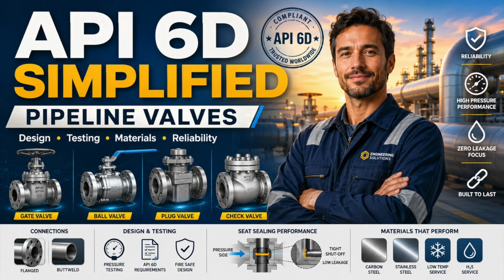And many of those errors will not appear during procurement. They will appear after installation. They will appear during commissioning. They will appear when a pig reaches a partially open valve. They will appear when trapped liquid heats inside a body cavity. They will appear when an actuator cannot move a valve under full differential pressure. They will appear when a check valve slams after a pump trip. They will appear when maintenance teams discover that the drain, vent, or injection point cannot be reached.